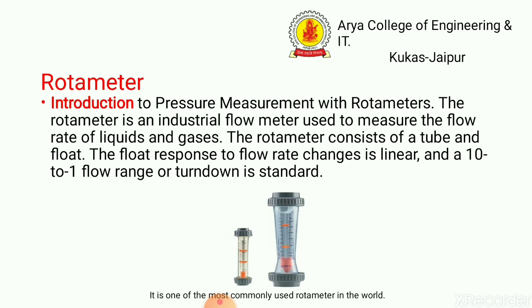Now we discuss the Rotameter. A Rotameter is a device that measures the volumetric flow rate of a fluid in a closed tube using pressure measurement. The Rotameter is an industrial flow meter used to measure the flow rate of liquids and gas, and it consists of a tube and float. The float response to flow rate change is linear, and a 10 to 1 flow range or turndown is standard.